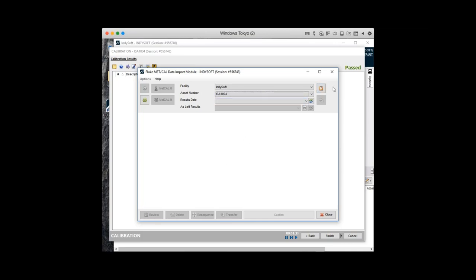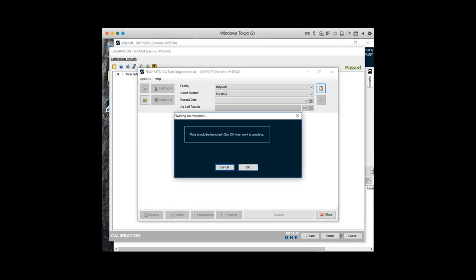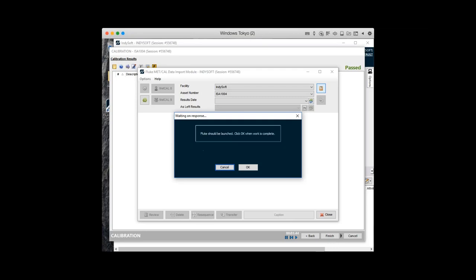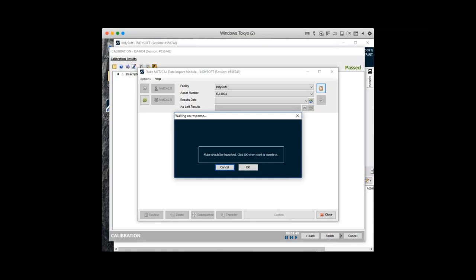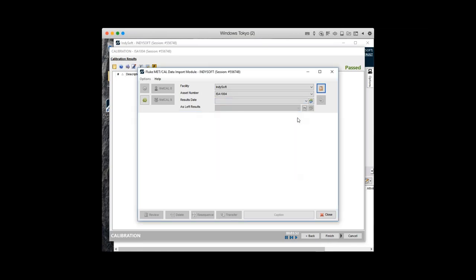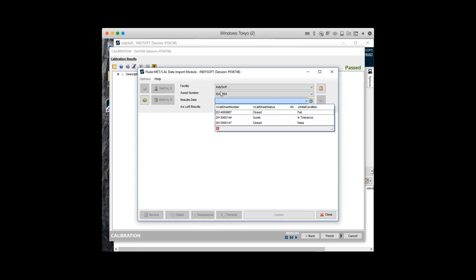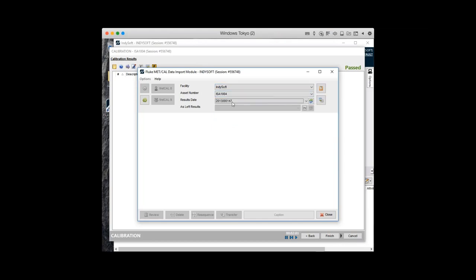There is a button to launch into the Fluke MetCal utility, which will bring up Fluke MetCal and a dialogue letting you know you should be working in Fluke. If you alt-tab back you'll see a reminder to finish up in Fluke before returning. Once you're done with your Fluke procedure you simply click the dialogue to continue. For the manual process, we already have our company and asset selected and I'm going to pick the most recent calibration. There is also an option to pick an as-left calibration, so we still have the merging capability of two different MetCal calibrations into one IndySoft event. There are also refresh buttons so if you're working externally in Fluke MetCal and have added new events, you can just hit refresh and it will refill the combo box with the latest information. Once we have this targeted information, all we do is click the import button.